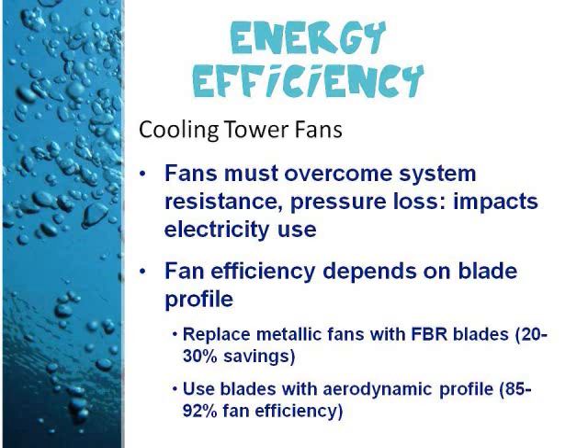with optimum twist, taper, and high coefficient of lift to coefficient of drag ratio. However, this efficiency is drastically affected by factors such as clearance, obstacles to airflow, and inlet shape. Cases have been reported where metallic or glass fiber reinforced plastic fan blades have been replaced by efficient hollow FRP blades. The resulting fan energy savings could be 20% to 30%.